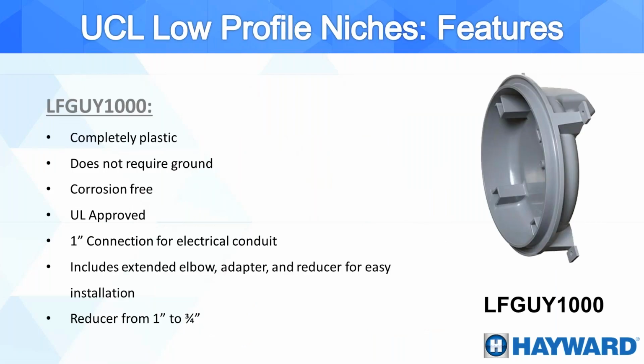Now we're going to take a look at some of the installation recommendations that we offer. If you have a customer that is building a new pool, they want to use the pool size light, now instead of having to use the standard niche, which we know is big and bulky, now we can use this low profile niche that is going to be suited for our ColorLogic pool lights. Good thing with this niche, it is totally plastic, so it doesn't require any grounding or any bonding, because remember, our pool lights don't require grounding or bonding either.